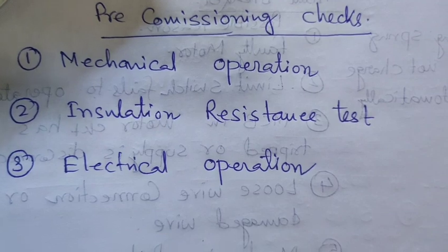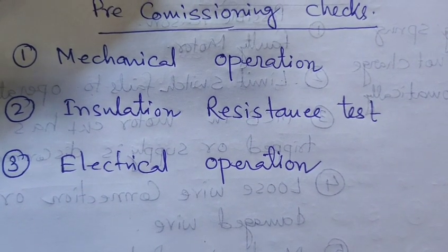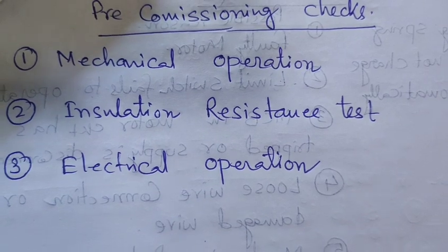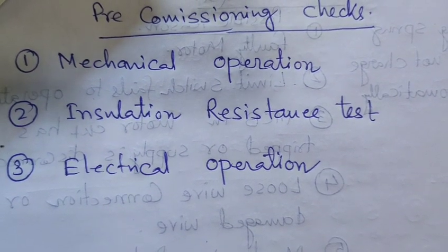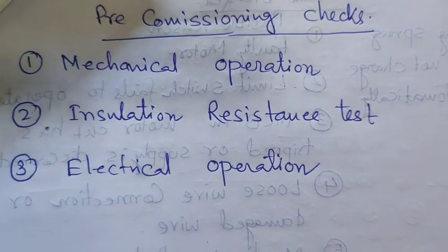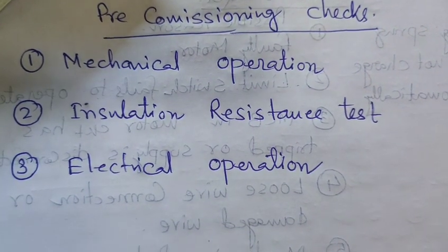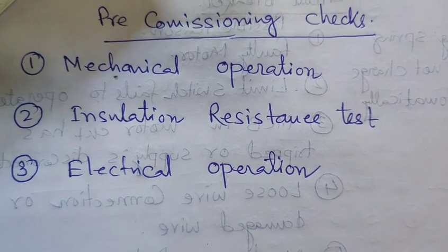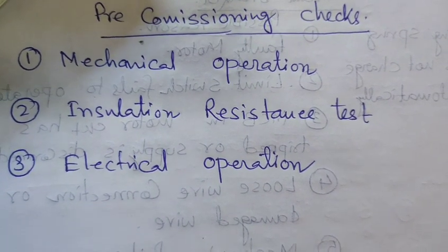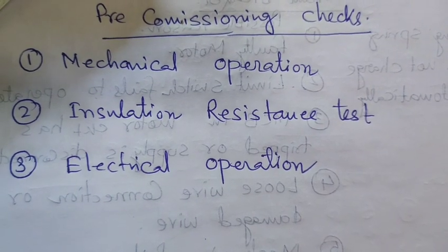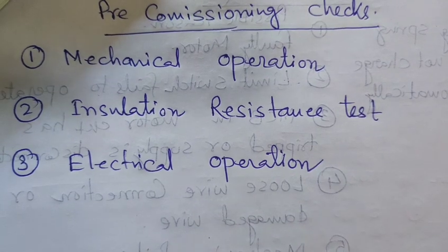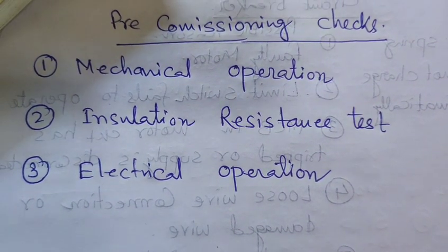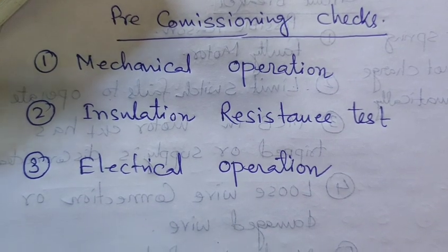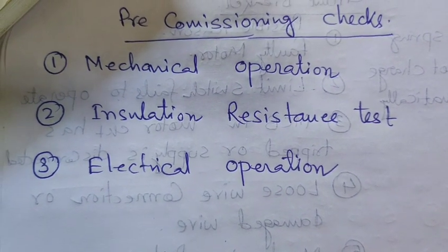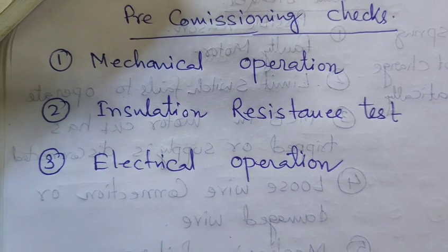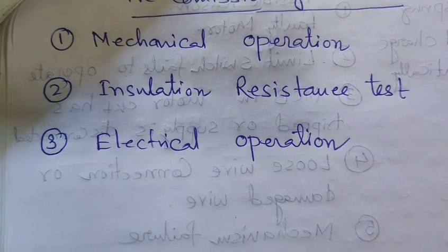If you are getting an insulation resistance of 100 mega ohm, it is an acceptable value for the 36 kV circuit breaker as per the IEC rules. If its value is less than 100 mega ohm, because of intrinsic particles or some voids or whatever may be inside the circuit breaker porcelain parts, HV testing should be recommended, and you have to consult with the testing if the value of the circuit breaker top and bottom is below the 100 mega ohm. It is very important to remember.